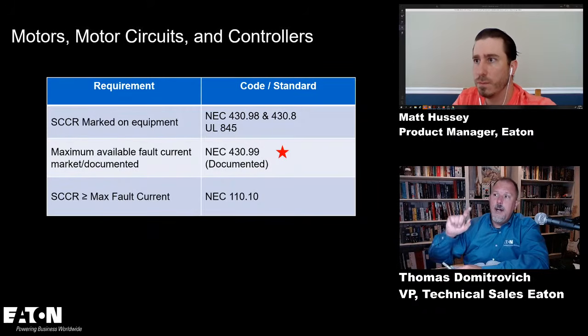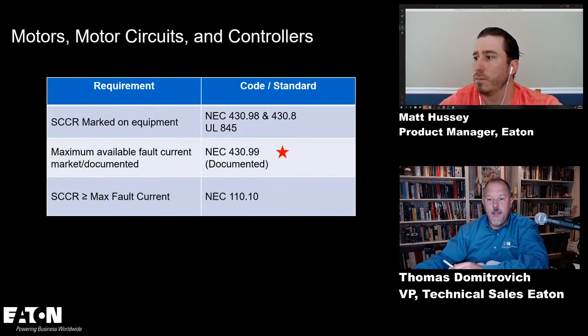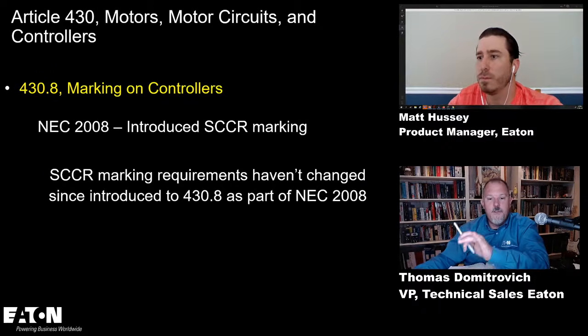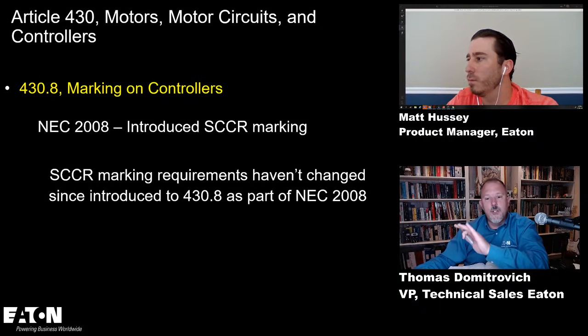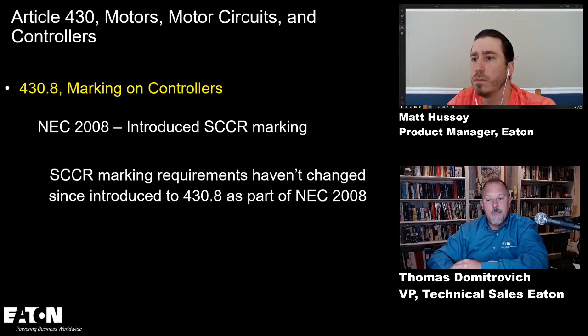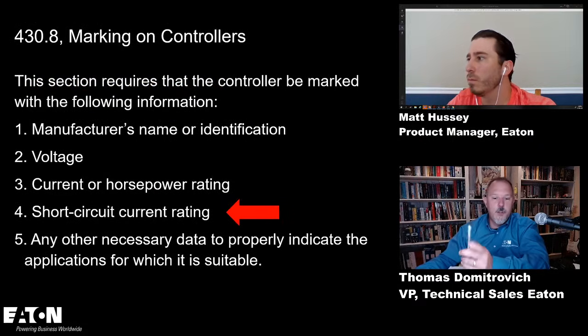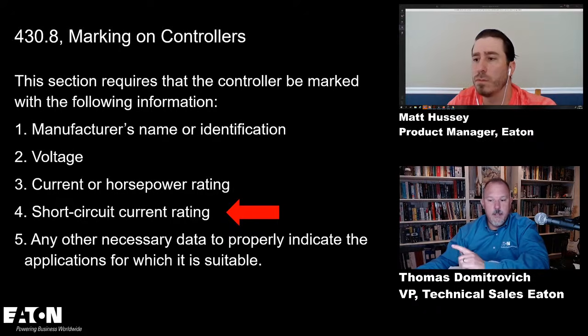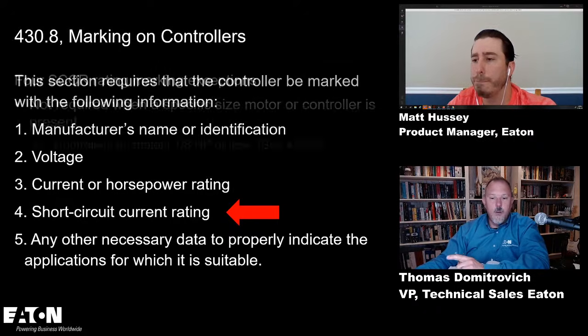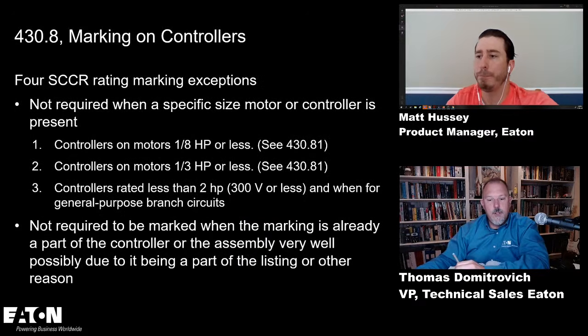And then you always have, based on 110.10, you have to make sure that the short circuit current rating is greater than the maximum available fault current at that equipment. And 430.8, the marking on those controllers, was entered into the National Electrical Code during the 2008 cycle, but really the standards cover you. So 430.8 short circuit current rating is item number 4, and then you look at that.